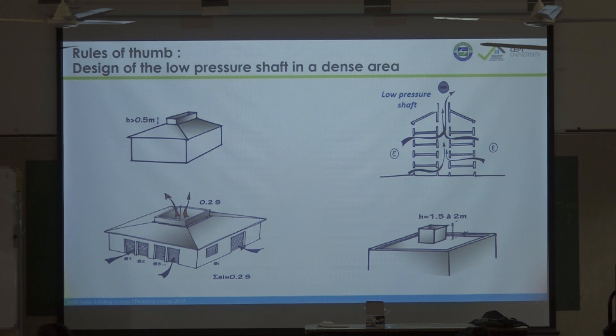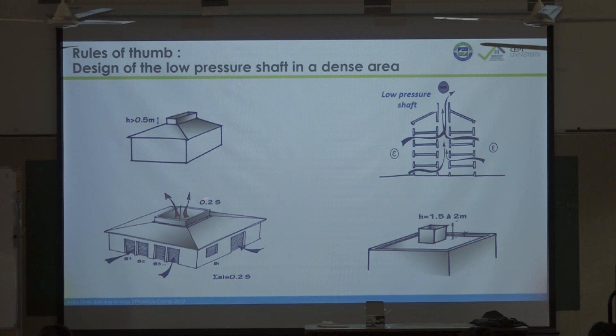Some rules of thumb: what is the height of the shaft and what is the surface? For a sloped roof, you need a height of at least 50 centimeters — 1 meter is better. The shaft area must be at least 20 percent of the total surface of the building. For a terrace roof, you need at least 2 meters height — 3 meters is better.